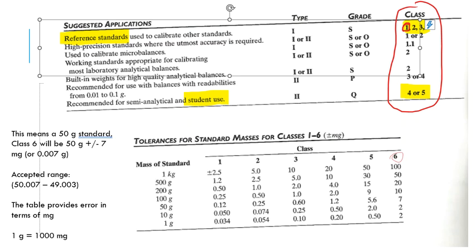So if you look at this very top line, it says reference standards. These are industry grade reference standards that have been double checked by third parties to ensure that if it says 10 gram, it really is 10 gram. Very often those are classes 1, 2, 3, and possibly 4, but you need to read the descriptions of the calibration sets, because they will tell you if they have been certified by another company. So that has to be part of the description.